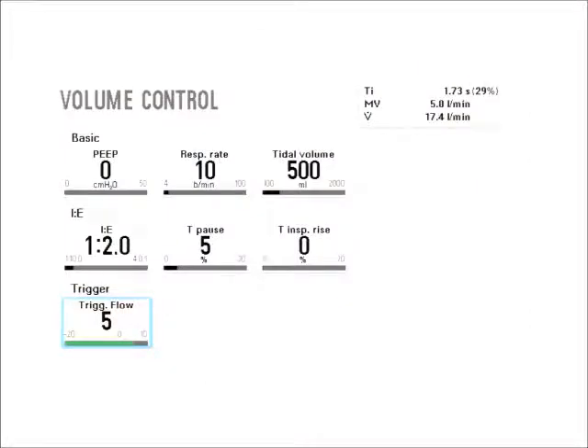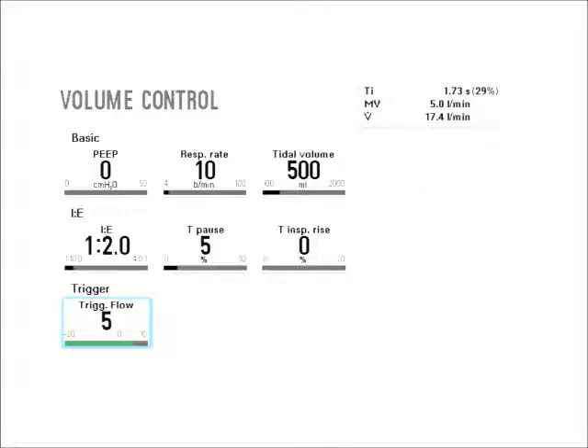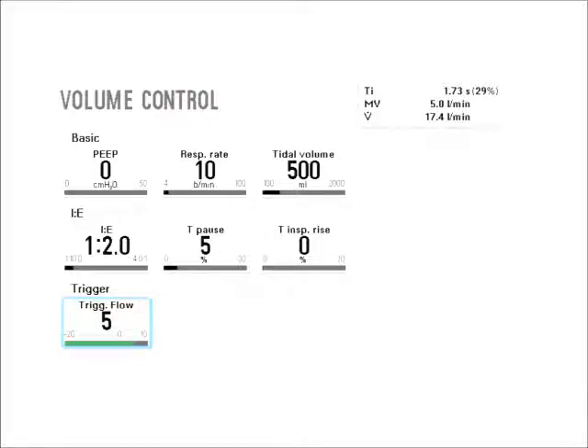But if we take a look at most ventilators today, we don't set an inspiratory time and we do not set an expiratory time at all. We're setting a frequency all together, and we're setting an I:E ratio or I time percentage or just an I time itself.